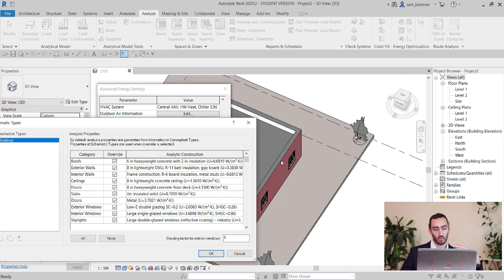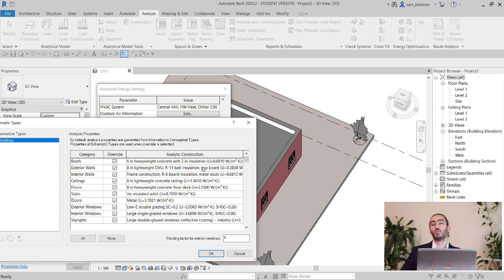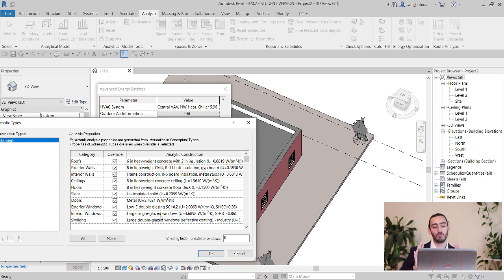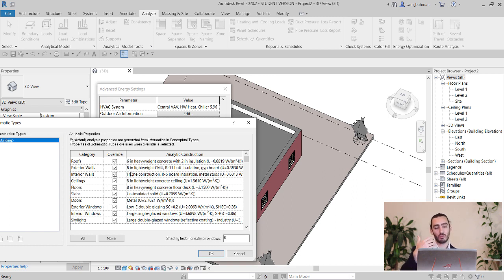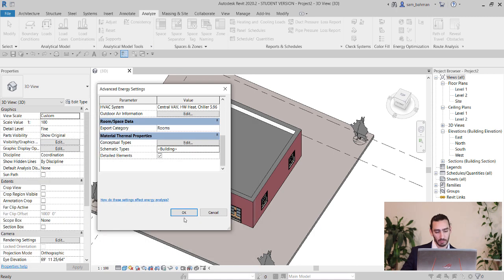Since we already checked these override boxes and set up this table, we have peace of mind that the U-values or R-values Revit will use for the energy analysis are in good condition. You need to make sure to repeat this same process for each element. Simply click OK.